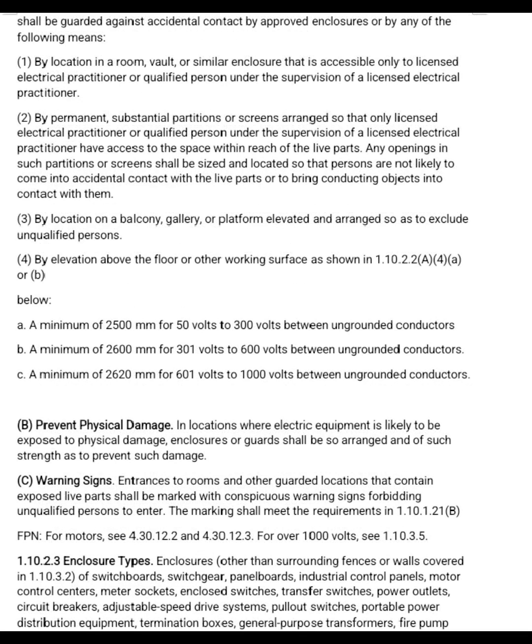Number 1. By location in a room, vault or similar enclosure that is accessible only to a licensed electrical practitioner or qualified person under the supervision of a licensed electrical practitioner. Number 2. By permanent substantial partitions or screens arranged so that only a licensed electrical practitioner or qualified person under the supervision of a licensed electrical practitioner has access to the space within reach of the live parts. Any openings in such partitions or screens shall be sized and located so that persons are not likely to come into accidental contact with the live parts or to bring conducting objects into contact with them.